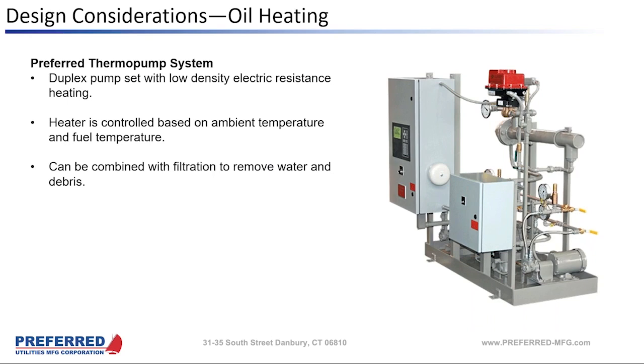So another way we do this is with a thermopump system. A thermopump system is basically just adding an electric oil heater to a duplex pump set. And the photo that you see on the right here shows a duplex pump set with one electric heater. I did a bunch of systems in Dallas after 2021 that had two heaters because the idea was we're going to have duplex pumps, we had to have duplex heaters. And we haven't had a cold spell like 2021 since then, but these have come on and have run a couple of winters in a row.